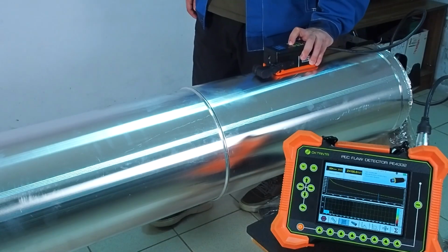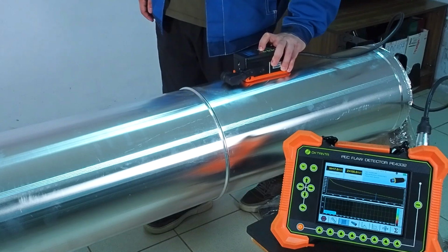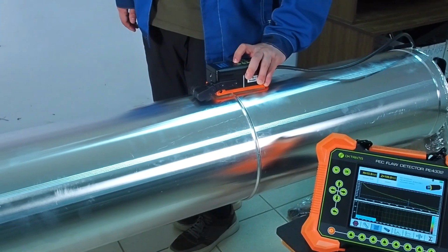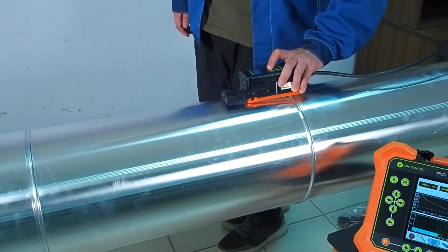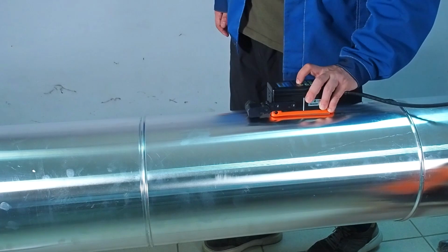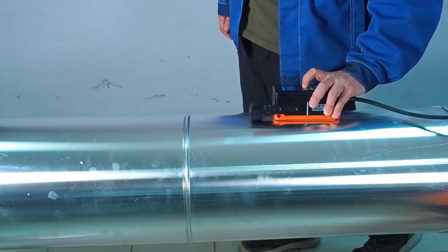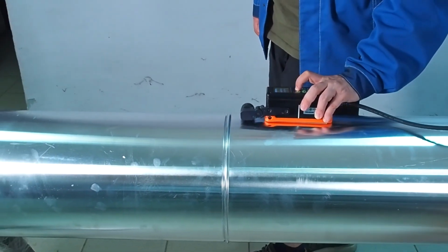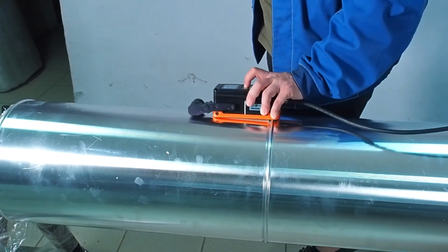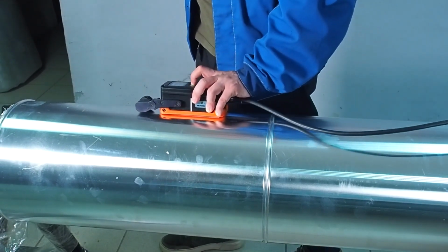The second option of plotting the C-scan is useful when the required grid is unavailable and you don't have time or possibility to chalk it. A special wheel can be attached to the sensor. Using this wheel, you can carry out the test with lines. The wheel encoder measures the horizontal coordinate of the sensor, and the operator takes measurements at equal intervals.